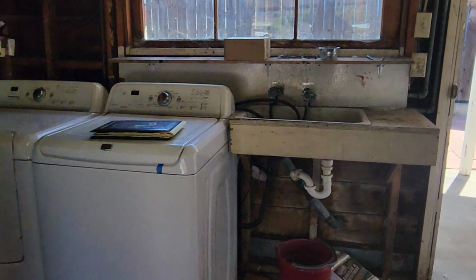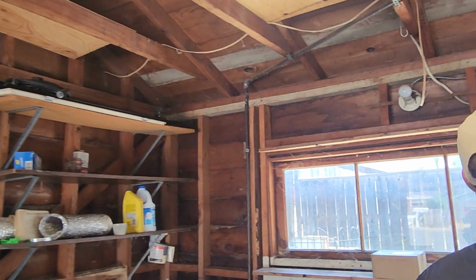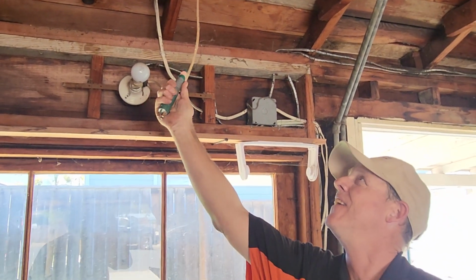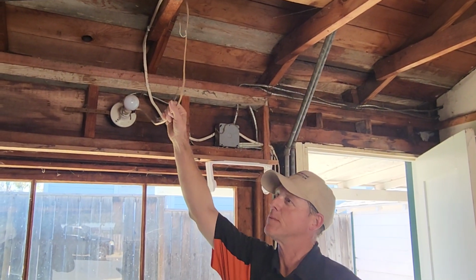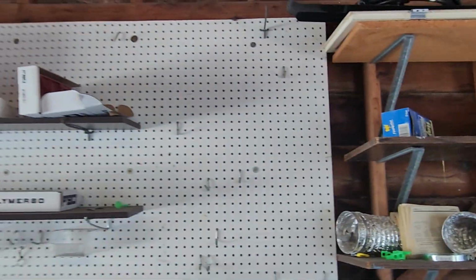Then the outlets in the garage should have ground fault protection, and then exposed Romex. I mean, this is okay. It is a little messy, but this one hanging here, it's a live wire. Oh yeah. It should go up and be buttoned up a little better. It's just hanging here for someone to grab. Right. All the way across. Yeah. Here's this outlet, open ground.